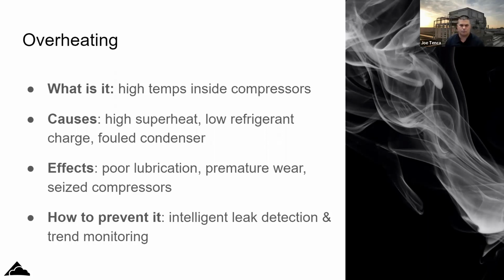Another one for me is the de-superheating of the compressor, whether it's a Y1037 valve or demand cooling. I think Bitzer's using the BMT kits now, is what they're called. De-superheating is essentially spraying a little bit of refrigerant into the suction header, or into the compressor body itself. I think a lot of people think, well, it didn't trip off, so it must be fine, but that's not necessarily the case. Sometimes those things are there to prevent it from tripping. The compressor may be running too hot and just hasn't hit the max point where it's going to lock out, but the added cooling is not working. I see it a lot. We see it a lot on these retrofits we do.